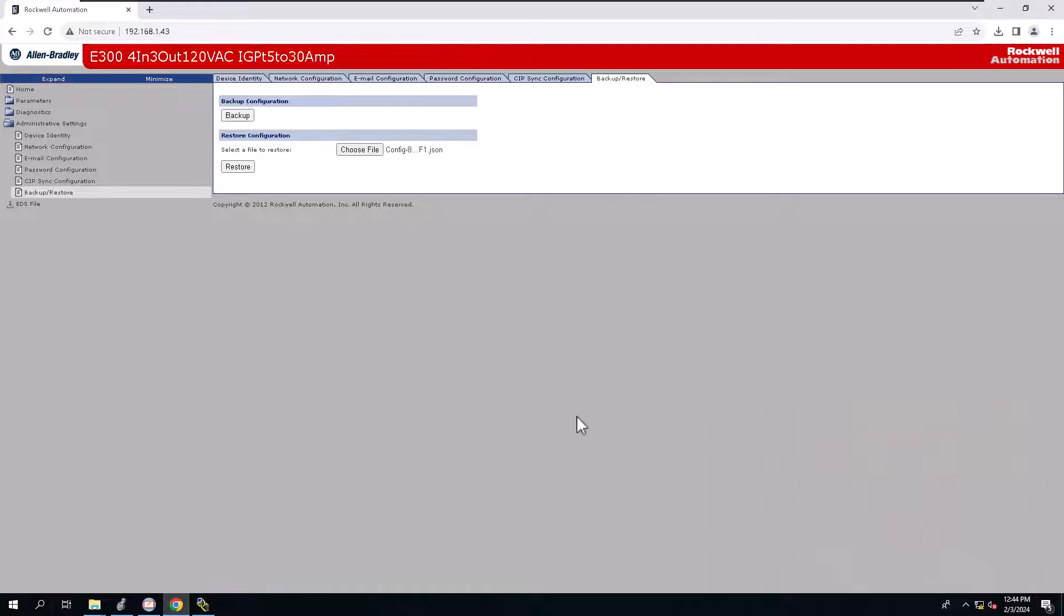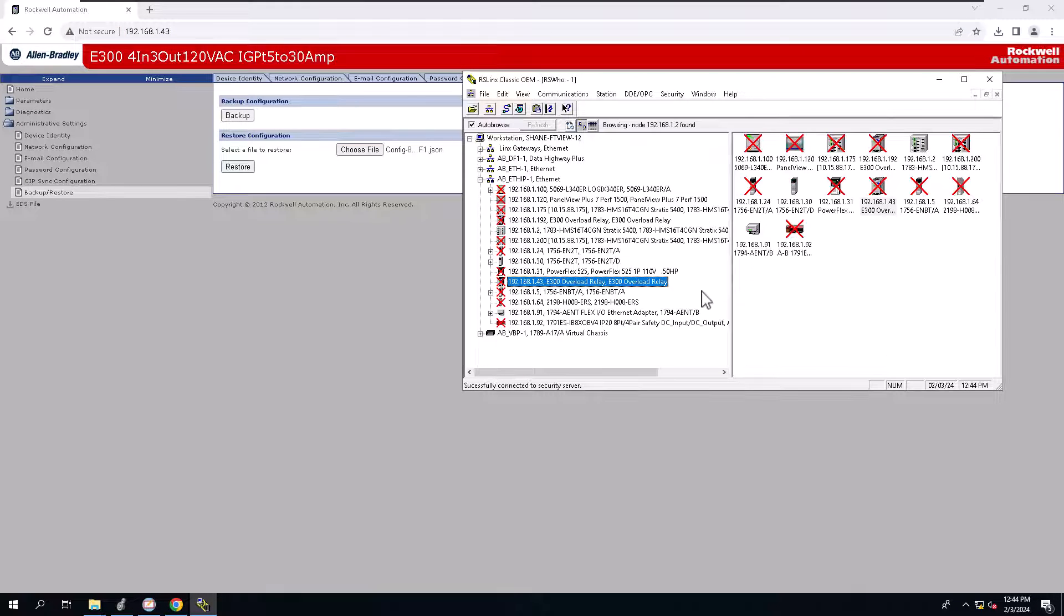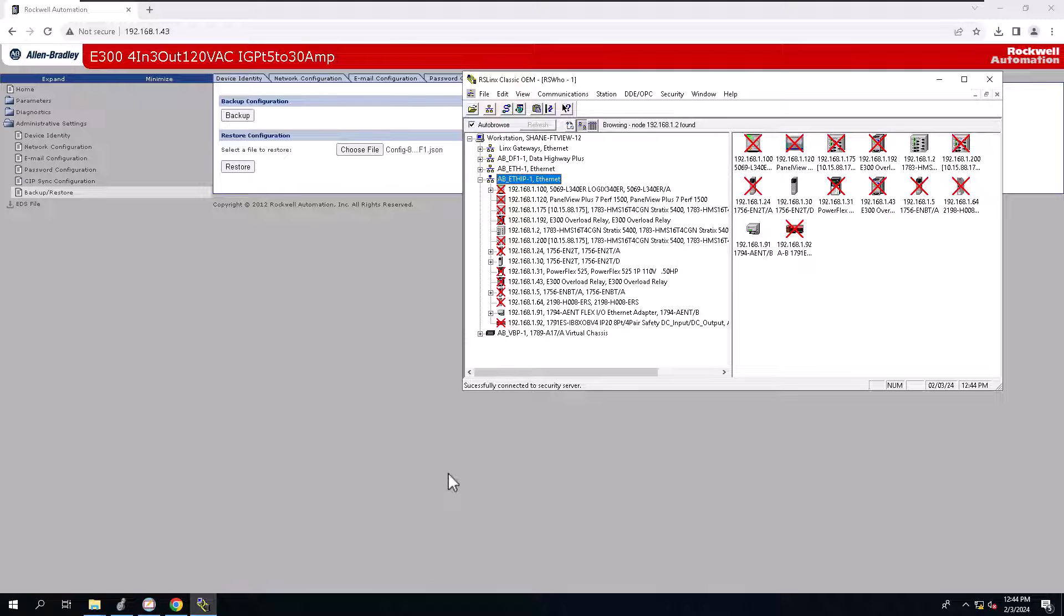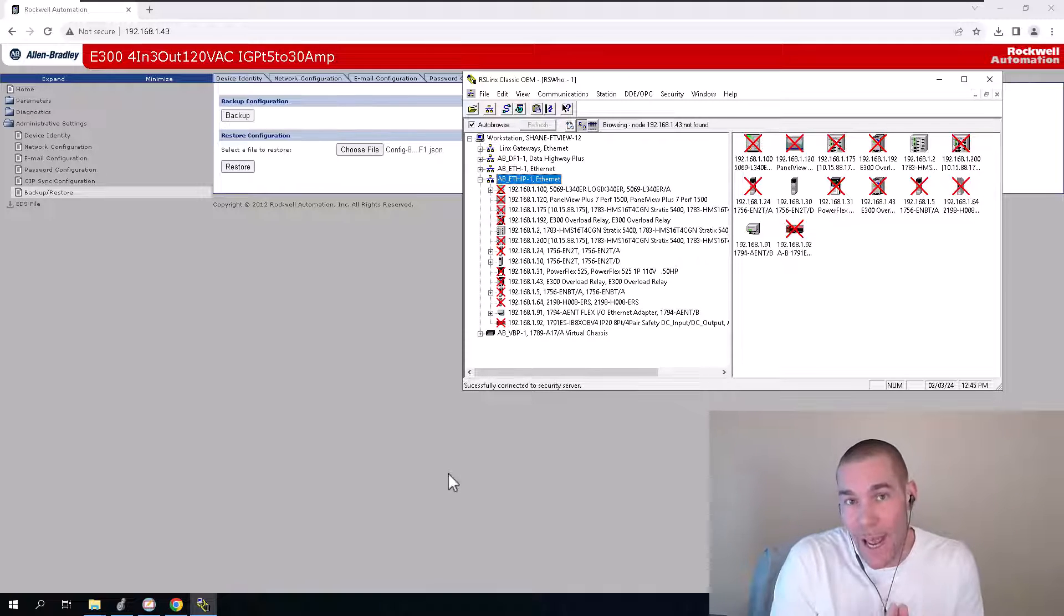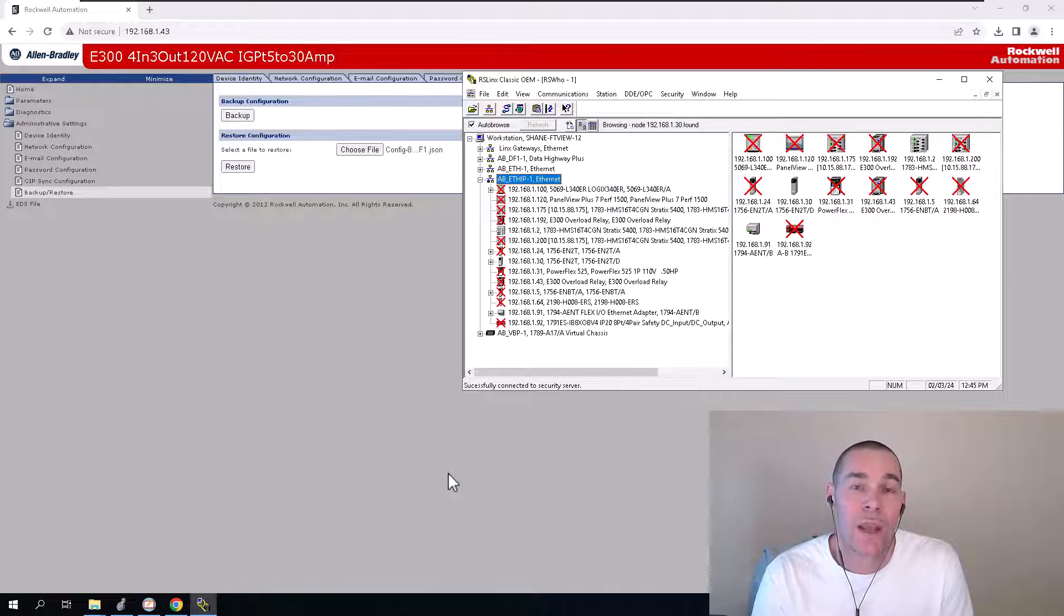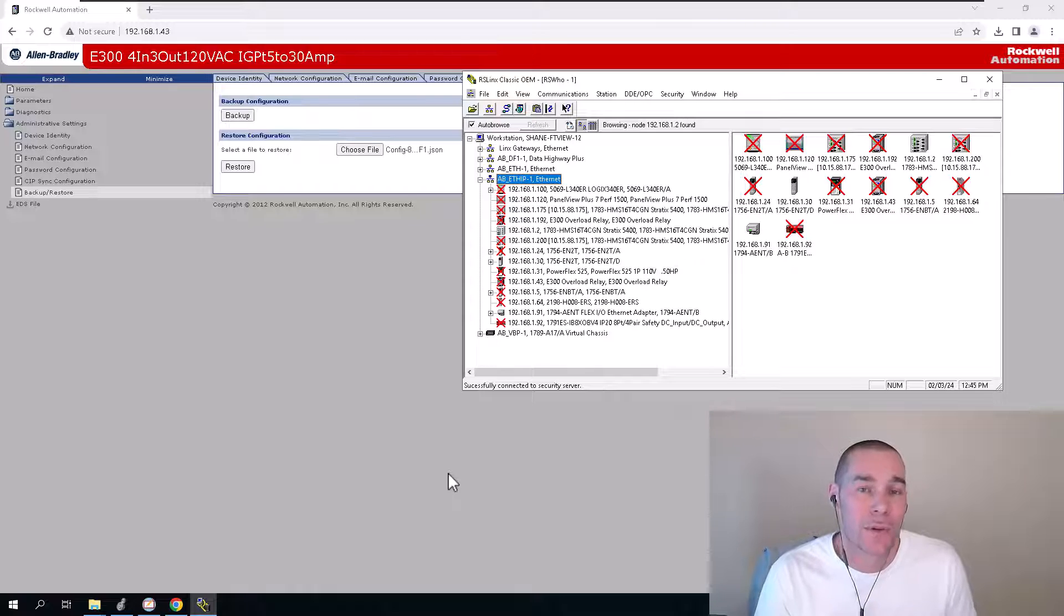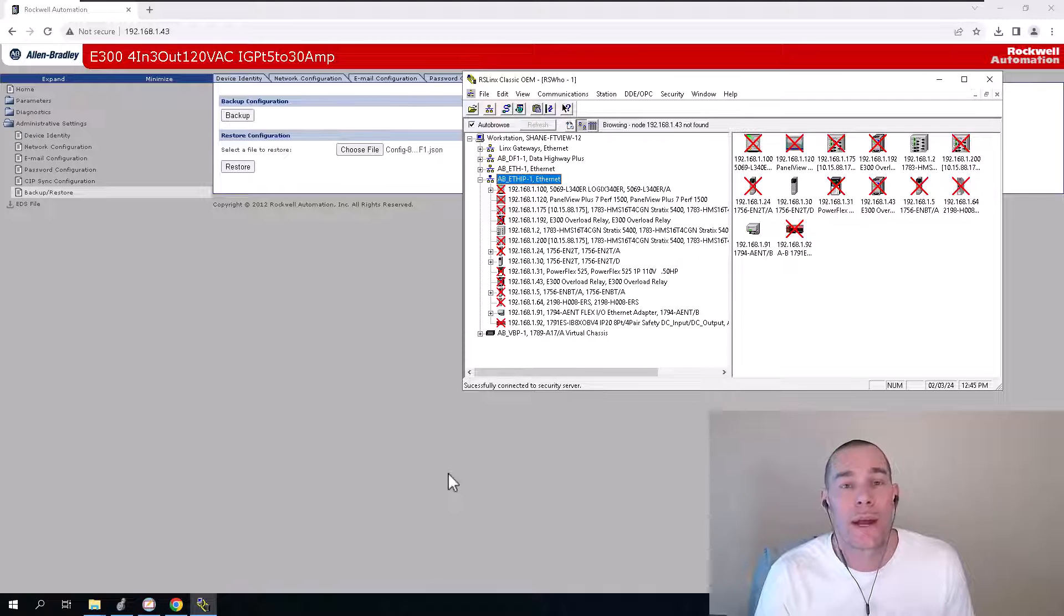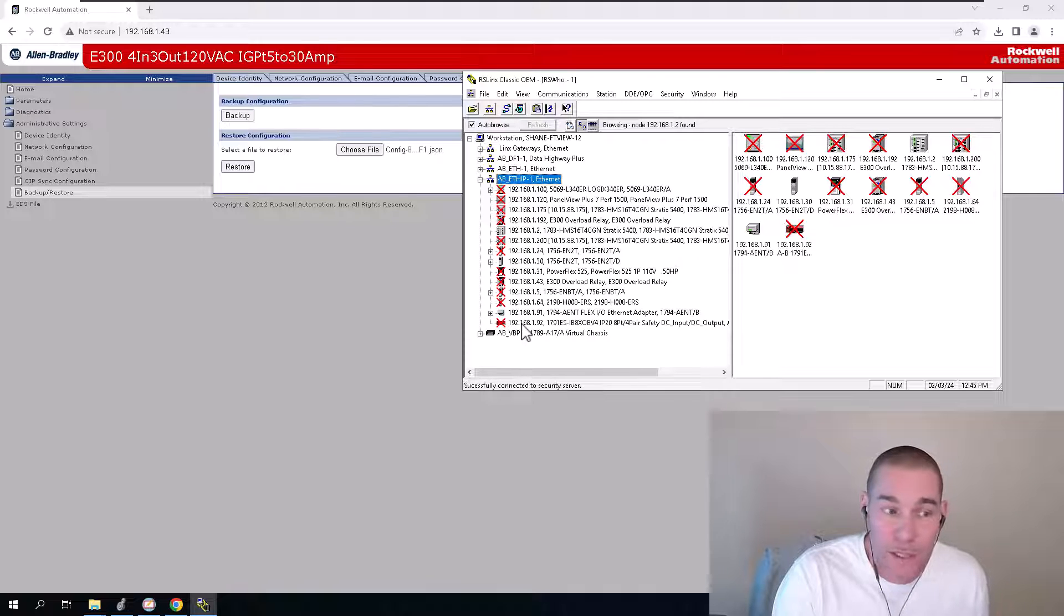So at this point, we're going to come in and wait till we have connectivity in RSLinx. And I'm going to show you that I no longer have access to the webpage. So in order to have access to the webpage, we have learned that we have to have the dip switches on zero, zero, zero. The first time we sign in, we use the administrator as the username and the password is going to be the serial number. So just keep that in mind.